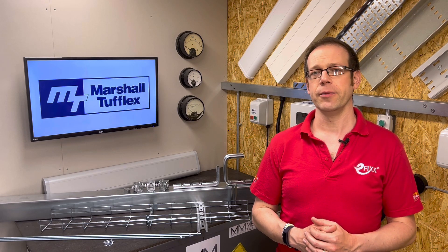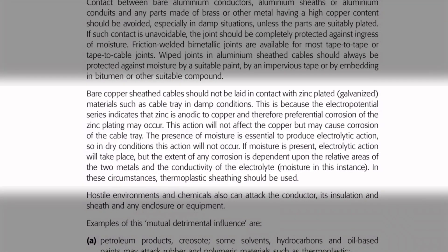There's one other drawback to galvanised steel containment as well. From Guidance Note 1: bare copper sheath cables should not be laid in contact with zinc plated or galvanised materials such as cable tray in damp conditions. This is because the electro potential series indicates that zinc is anodic to copper and therefore preferential corrosion of the zinc plating may occur. This action will not affect the copper but may cause corrosion of the cable tray. The presence of moisture is essential to produce electrolytic action, so in dry conditions this will not occur. In these circumstances, thermoplastic sheathing should be used.